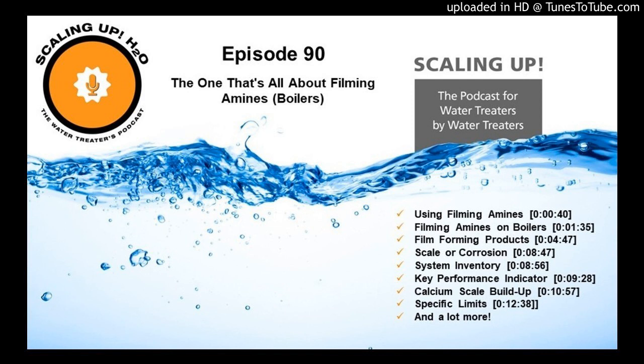What we do know with filming amines, what I've seen time and time again, is that with the application of filming amines, whether you're in a boiler or whether you're in a cooling tower or even in a closed circuit type environment, if we see deposition, calcium or other types of deposition, you can see deposit in low flow areas, but it deposits in a non-adherent form.